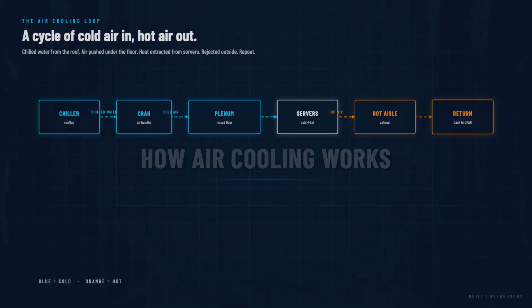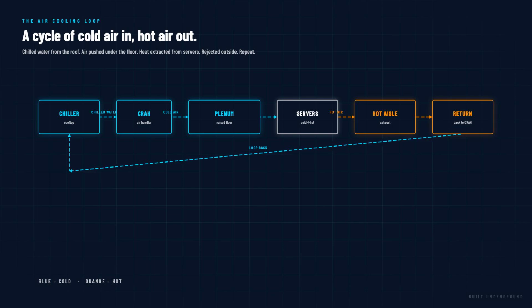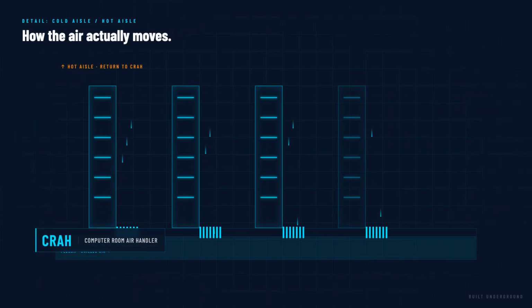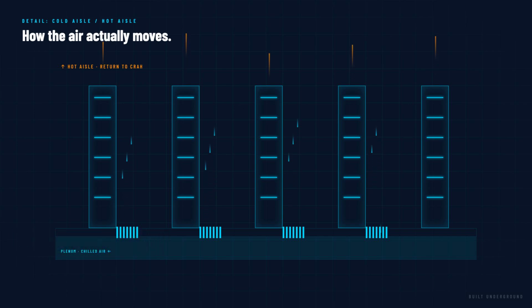Air cooling has been the standard since the first commercial data centers in the 1990s. The principle is simple: push cold air through the servers, heat the air, extract the hot air, and cool it back down. Repeat. In a traditional raised floor data center, computer room air handling units, called CRAHs, push chilled air into the space beneath a raised floor. That air rises through perforated floor tiles into cold aisles, passes through the servers front to back, exits as hot air into the hot aisles, and gets drawn back into the CRAH units to be cooled again.